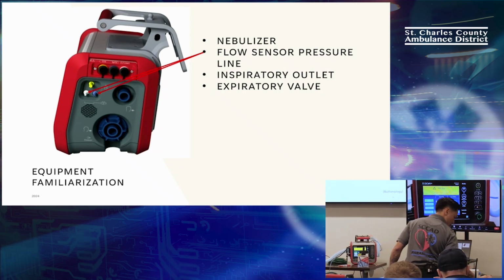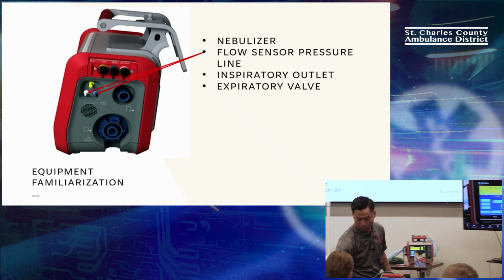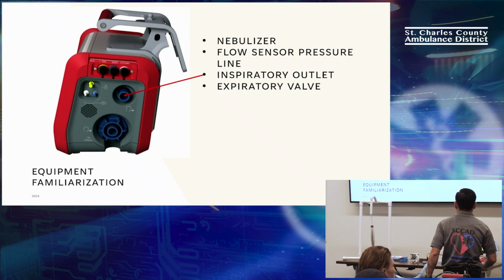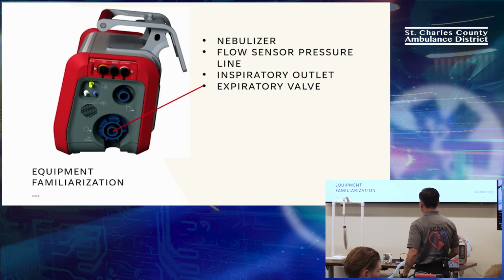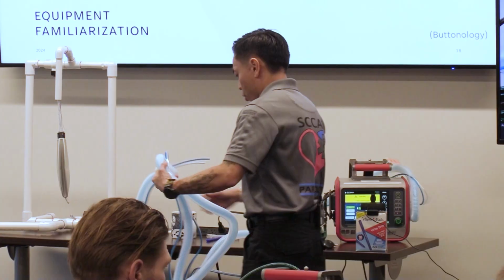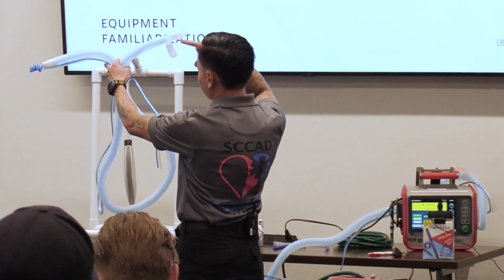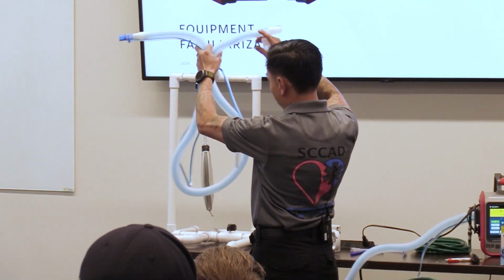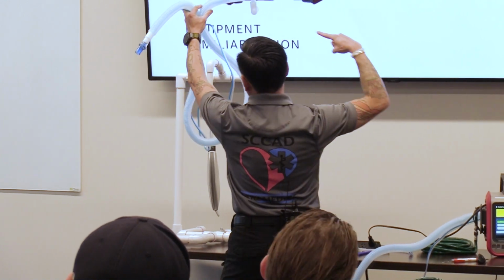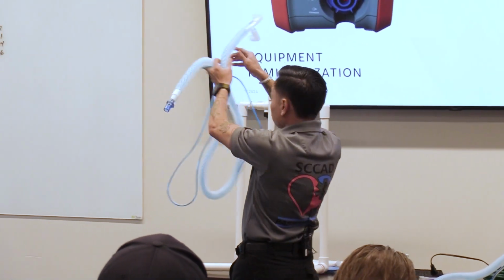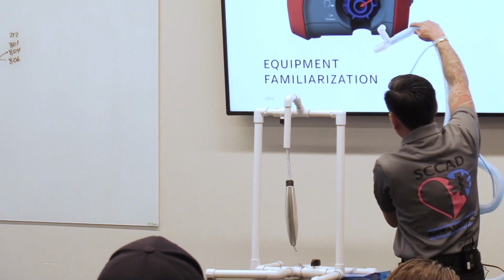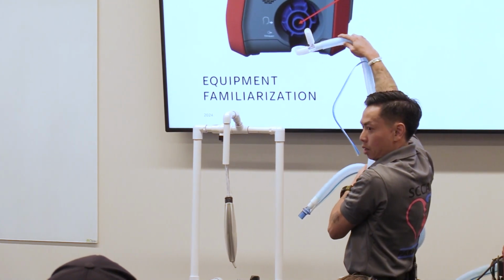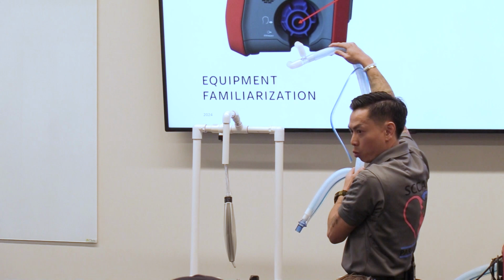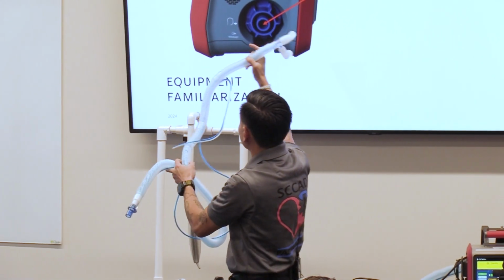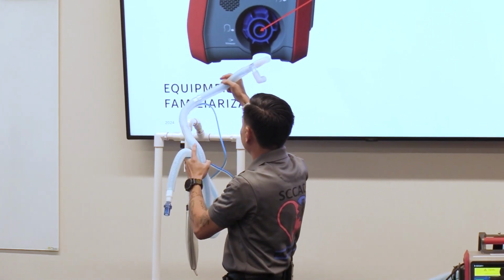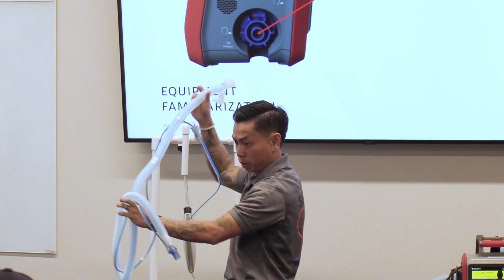So then you have that's the inspiratory outlet and the expiratory valve. If you look at your circuit, it's got this triangle, right? The chevron triangle or the tubing, whatever, should be facing towards the front of the ventilator. If your ventilator has a tail, it will still work, but it's not going to be too happy, right? So when you plug your circuit in, make sure that the chevron goes to the front of the ventilator and the tubing goes towards the front of the ventilator.